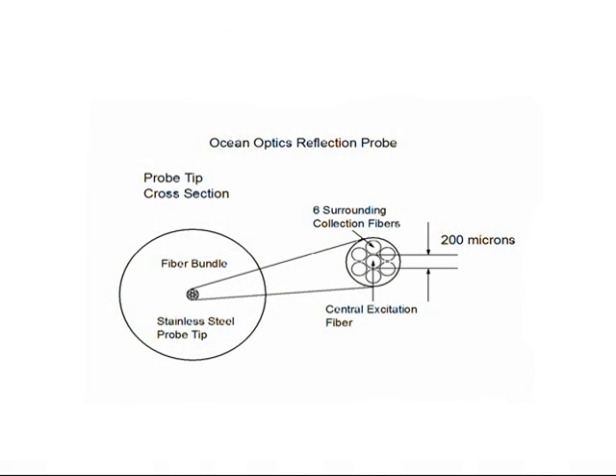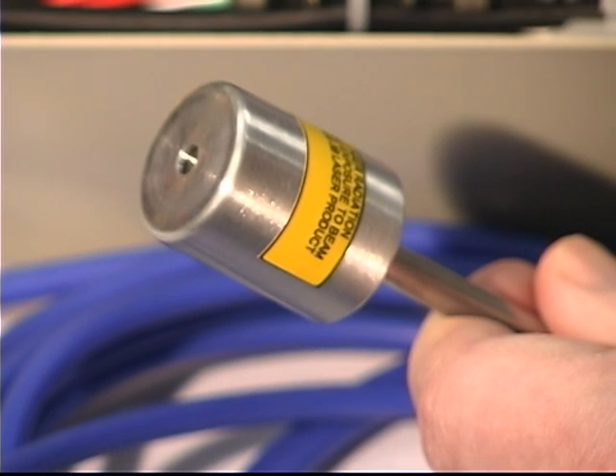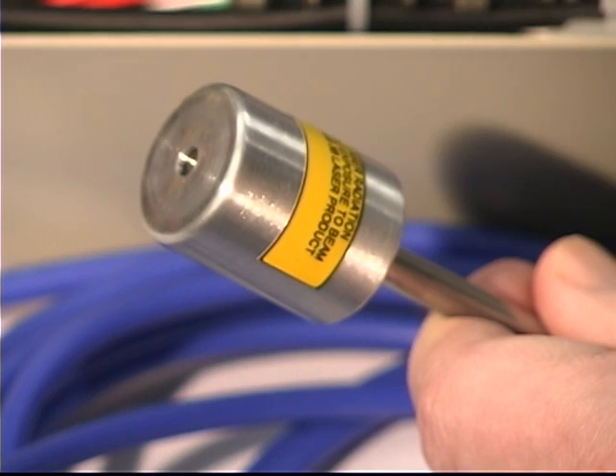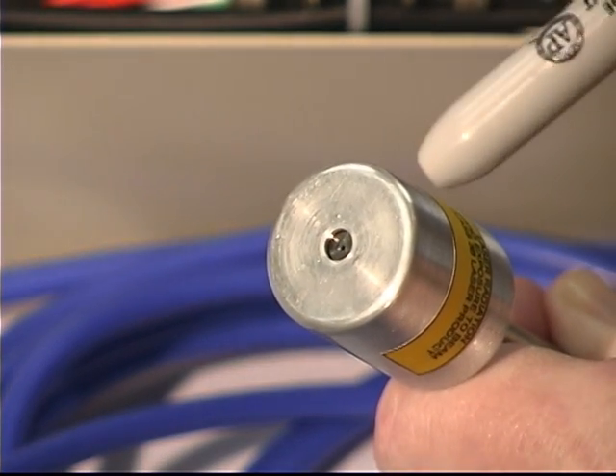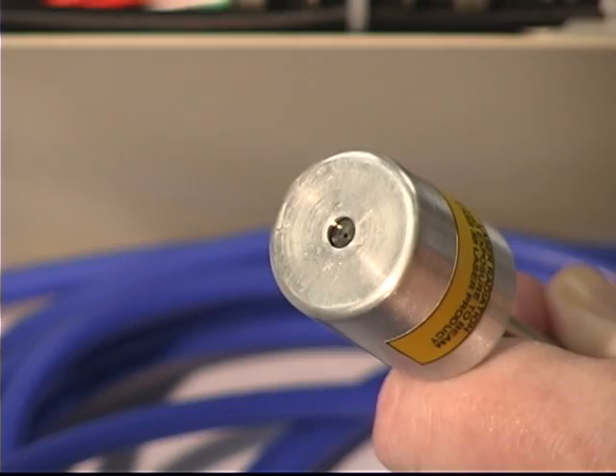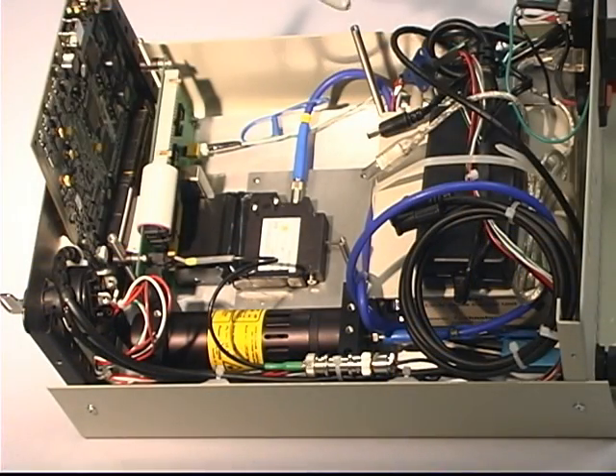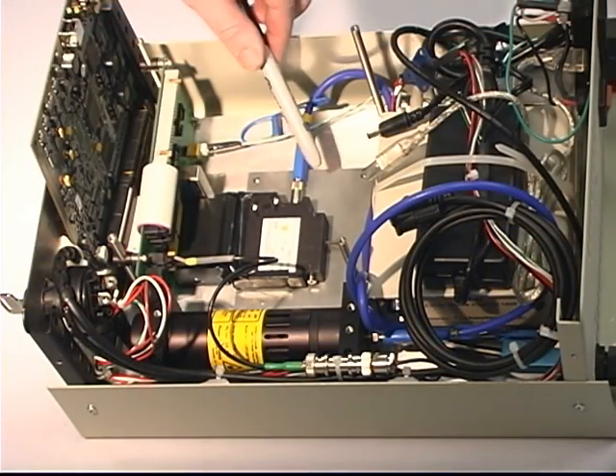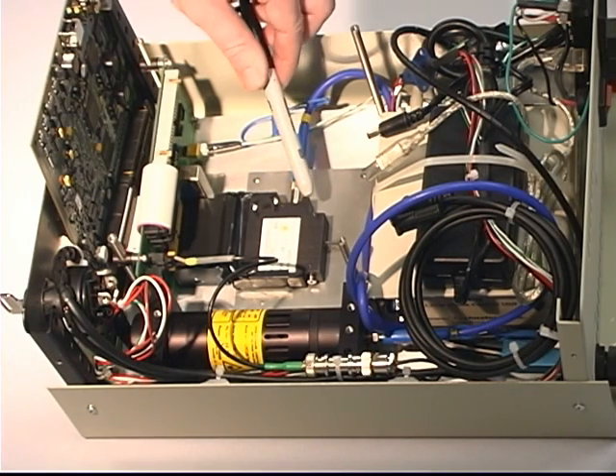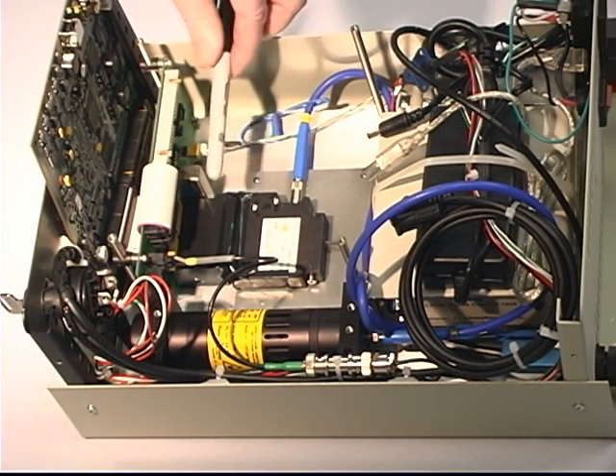This probe is comprised of seven 200-micron optical fibers in a 6:1 geometry. The central fiber is used to deliver the diode laser light, while the six surrounding fibers are used to recover the LIF emission and return it to the LIF unit for detection and processing. The reflection probe tip is mounted in a custom holder that both protects the fiber optics and positions the tip for optimal collection efficiency. Inside the LIF unit, light is coupled from a diode laser to the central fiber optic, while the six collection fibers are directed to the spectrometer for dispersion and detection.